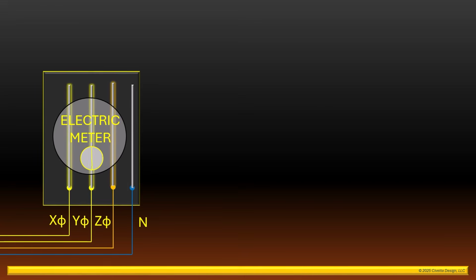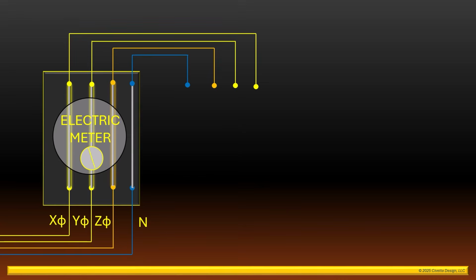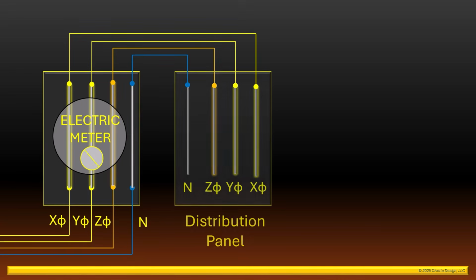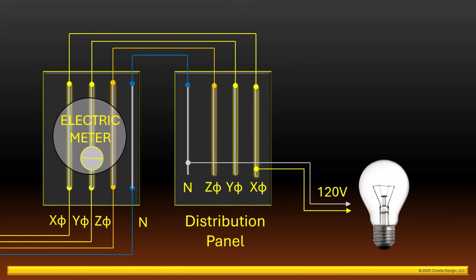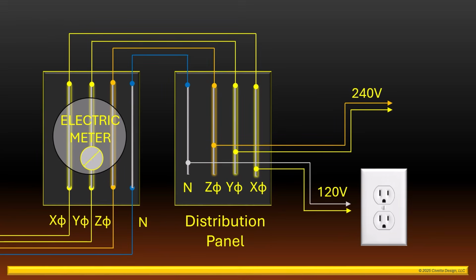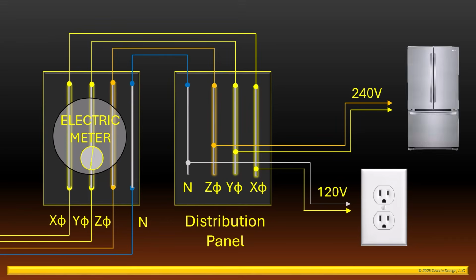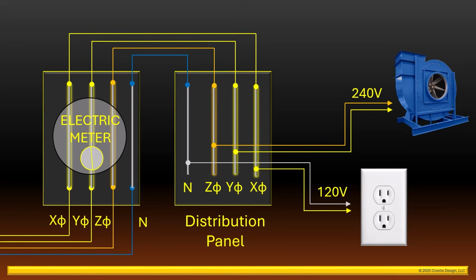Bus bars carry the current through the electric meter so the utility can monitor power usage. Another set of four conductors carry the power to the distribution panel. X phase and the neutral, or Y phase and the neutral, are used to provide single-phase 120 volt power to lighting, outlets, and other 120 volt appliances. Any two of the phases can be used to provide single-phase 240 volt power to electric water heating, refrigeration, or industrial machines requiring 240 volts.